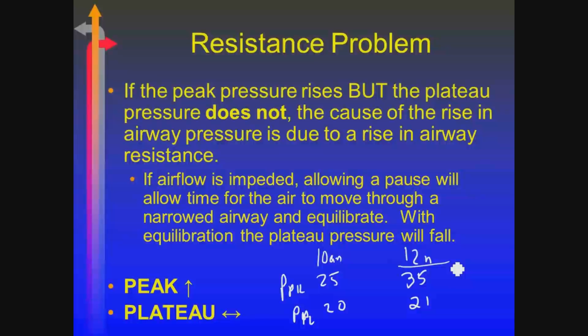All right, so resistance and compliance. Need to distinguish between the two of them because I'm walking into the ICU and I'm seeing my high pressure alarm going off. Which is it? Because the solution for a compliance problem is totally different than a solution for a resistance problem.